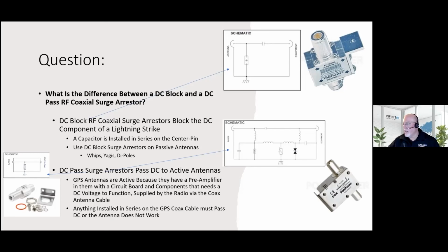And if you're calling me and asking which surge arrestor you would need for, like, a timing signaling network thing, GPS, then I would ask you what the antenna operating voltage is, which is not going to be the same as the radio's input power voltage. The radio will send whatever the antenna needs. It's typical to be 5 volts, 24 volts, something in that range. And the reason we ask that is because this particular product is our premier DC pass product. It's a hybrid using everything. And they're designed for certain voltages.